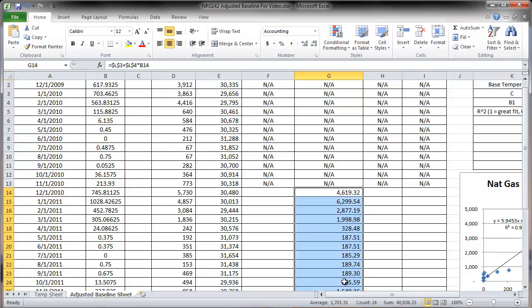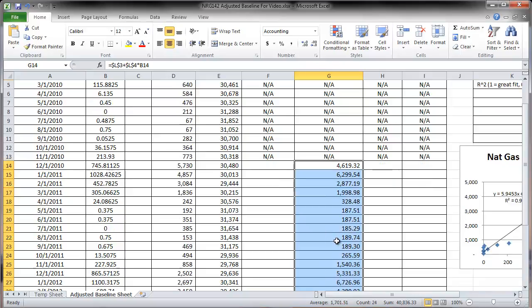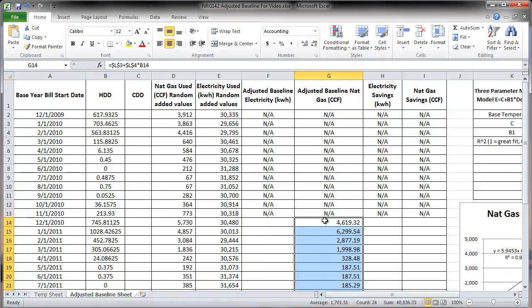The adjusted baseline gives us what we'd expect given changes in heating degree days or weather. From here you can calculate the percent difference between actual natural gas use and the adjusted baseline, as well as savings and other statistics. This tells you whether your building is performing efficiently given weather changes, or not as well as expected.